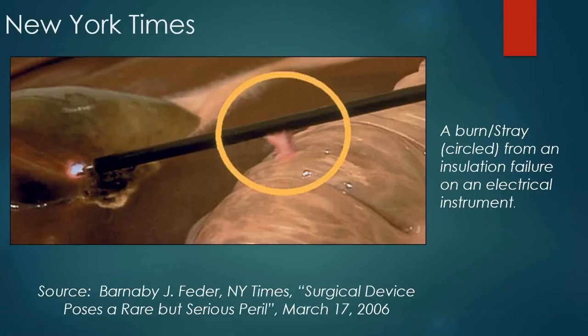The New York Times had an article here, and this is a good picture to describe that, a burn or stray circled there on an insulation failure of the electrical instrument. As you can see, that's out of that 10% range that would be seen during the procedure. No one would ever know.